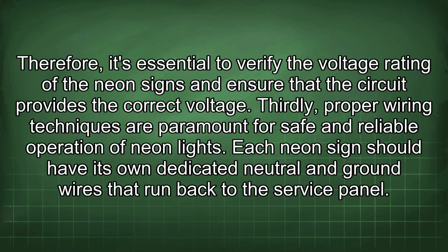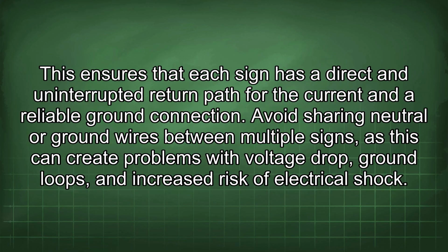Thirdly, proper wiring techniques are paramount for safe and reliable operation of neon lights. Each neon sign should have its own dedicated neutral and ground wires that run back to the service panel. This ensures that each sign has a direct and uninterrupted return path for the current and a reliable ground connection. Avoid sharing neutral or ground wires between multiple signs, as this can create problems with voltage drop, ground loops, and increased risk of electrical shock.